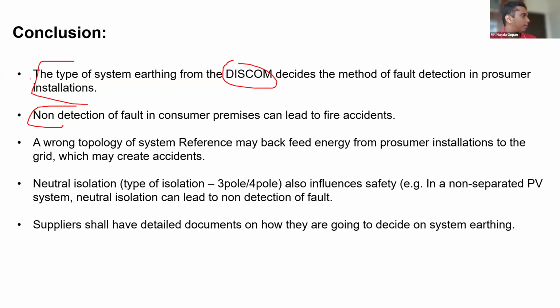Now, that is the third point. Next one is the neutral isolation. I have explained in the previous slides that most of the fault current in the non-earth, non-separated system will be flowing through the system referencing conductor, and then it will be flowing through the neutral of the conductor.